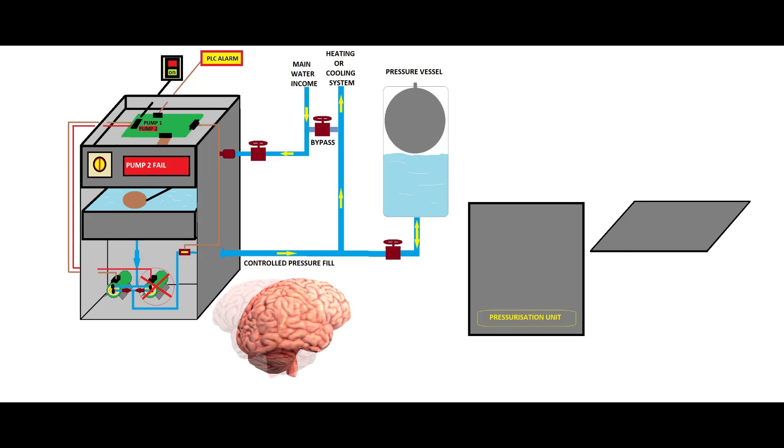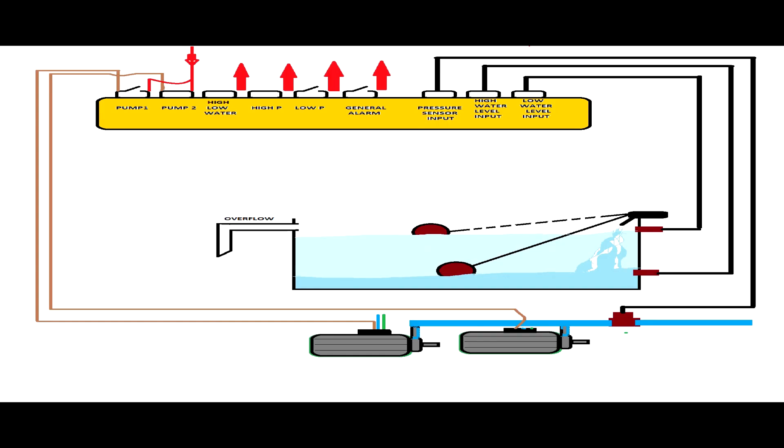So a very good idea in this situation if we have two pumps is to analyze quickly the printed circuit board. As you'll see we have two relays: relay number one which drives pump number one and relay number two which drives pump number two. But pump number two is faulty.